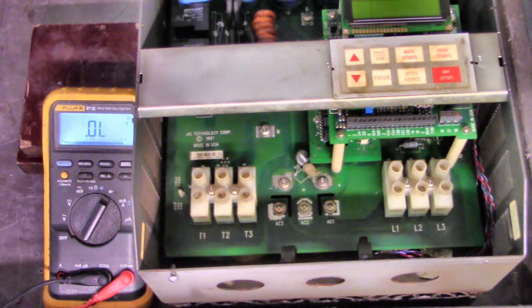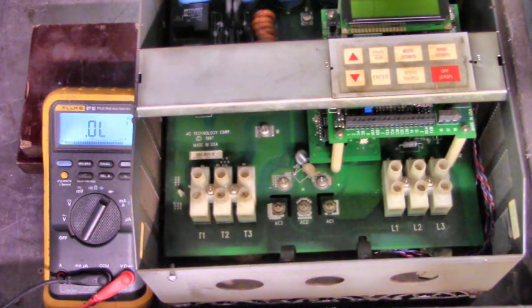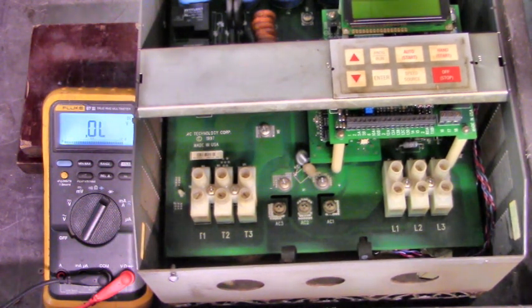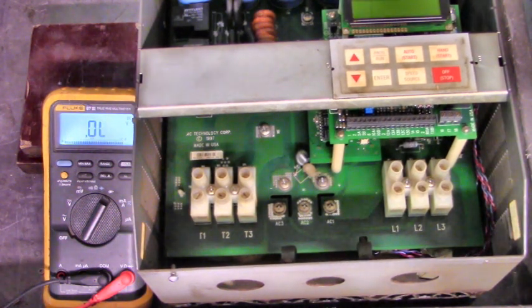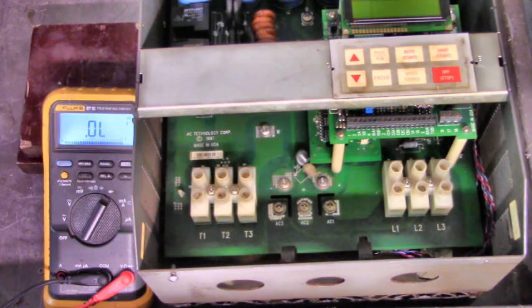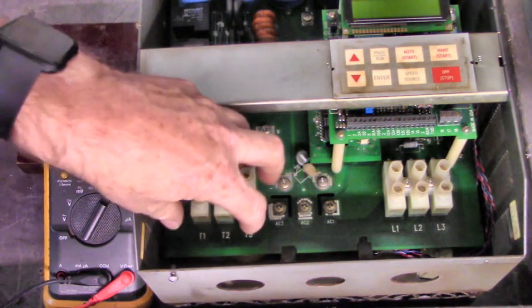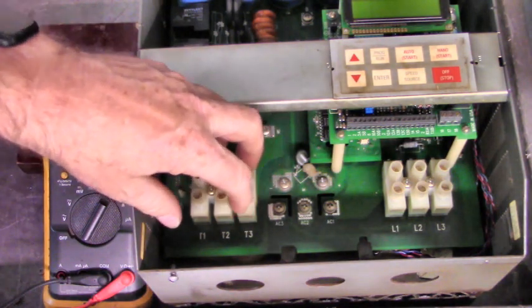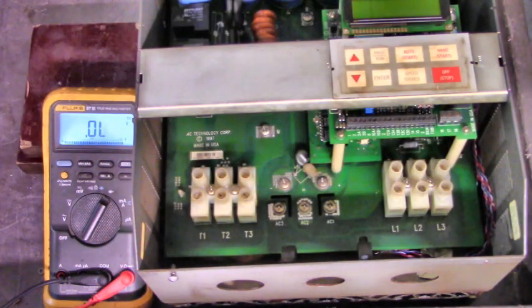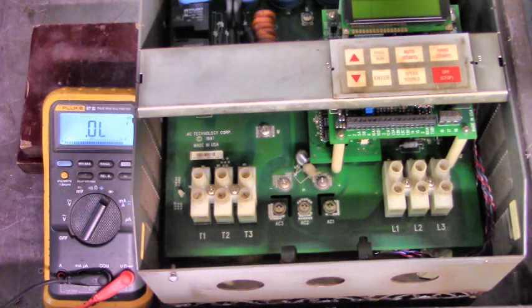Now, notice on this AC Tech, and this is the way it is on most of the AC Techs I've worked on, the motor's on the left side and the line's on the right side, so be very careful.